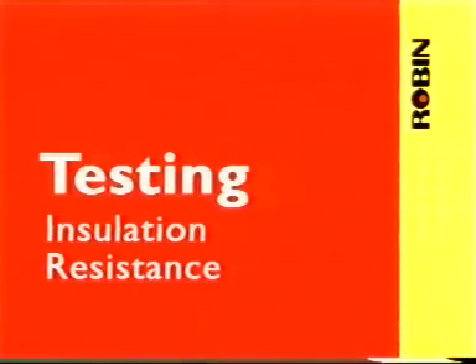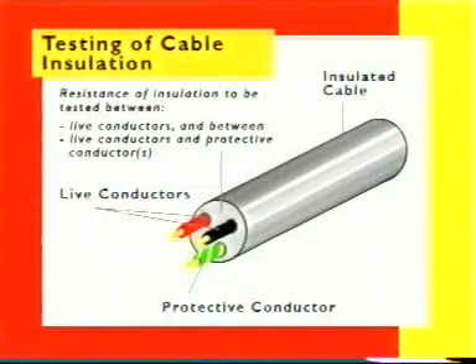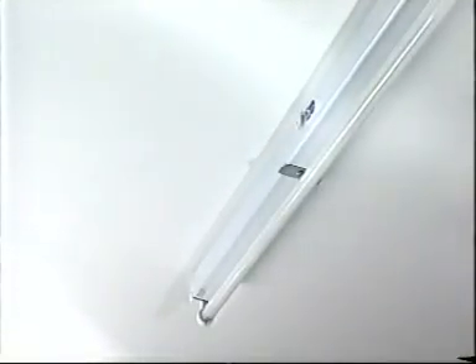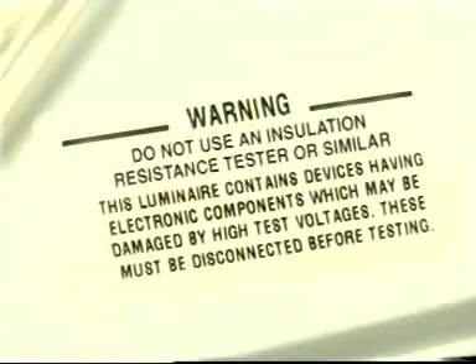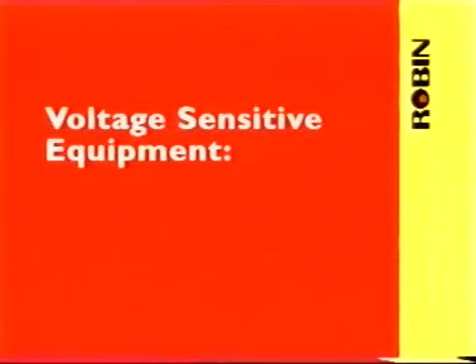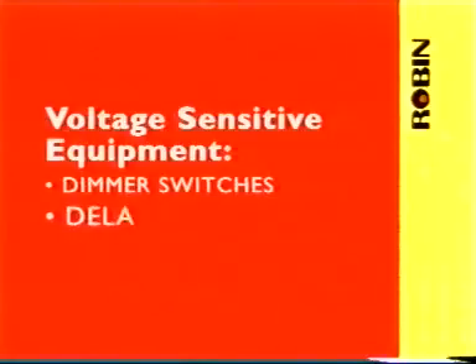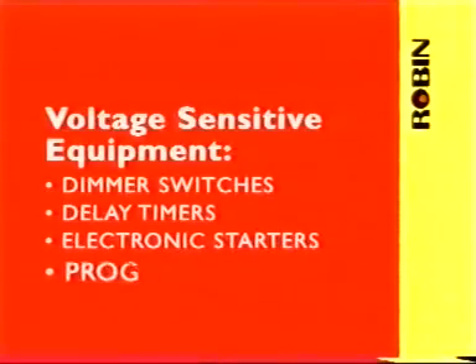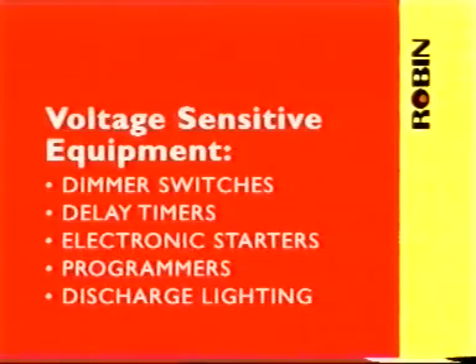Insulation of live parts is obviously very important to prevent risk of electric shock and to prevent excess current flow in unwanted paths. Its effectiveness must be tested between live conductors and between live conductors and earth. Before testing, it's important to disconnect equipment or take other measures to prevent damage to voltage-sensitive components on the circuit being tested, which may be damaged by the test voltage. Such equipment includes dimmer switches, delay timers, electronic starters for fluorescent lighting, and similar.